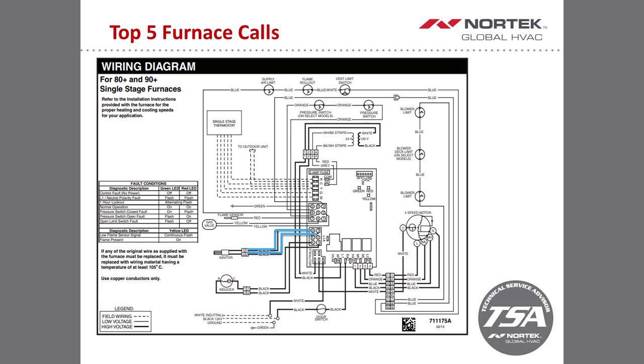From an igniter standpoint, just make sure you're getting line voltage to it when it's required, and if you're not, you may either have an igniter problem or a potential board issue. What I have here is off of a single stage furnace wiring diagram. You have a 6-pin Molex plug, and what I have highlighted here, you'll have 2 black wires that go directly to the igniter. Between the Molex plug and the igniter, there is a 2-pin connector or Molex plug for the actual igniter. So if the igniter is not warming up and we need to test voltage, just unplug that 2-pin Molex plug, put your meter leads on there, and see if you're actually getting line voltage from the board. That will direct you in a direction if you have an igniter or a board issue. But there is a 2-pin Molex plug connection there, just as a reminder.